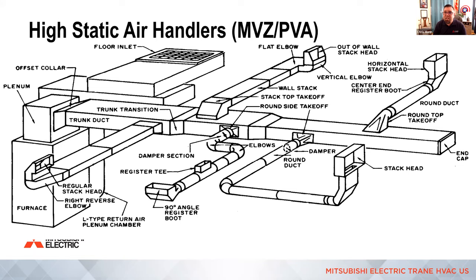Steve asked, is it recommended to always have that dead head end cap like that? Absolutely. So that's a rule of duct design. I'm going to cover the 10 rules of duct design right after I get through this example. You actually have to have that static pressure built up in the trunk for the air to make the turn. And you need to not be within a foot of that end cap. So yeah, we're going to walk through those, because what ends up happening, I find, is when a system's not operating correctly, a lot of times it's duct design and you need to figure out what item to fix. I would say that's the first item to look for, because if you take anything off that end cap, not like a low static, but on a mid or high static, it depressurizes the whole trunk and all the air goes to that one run. All right. So we'll get to that though.